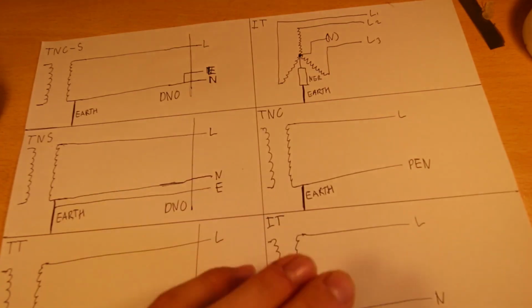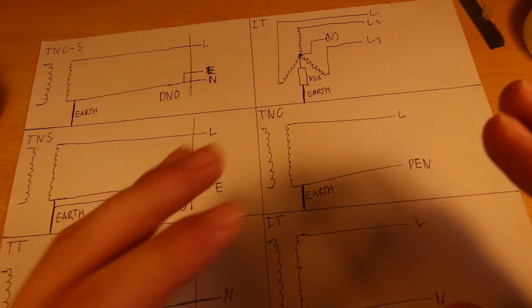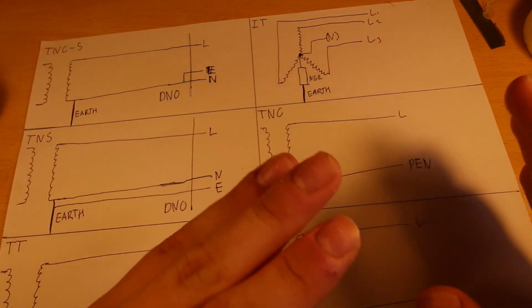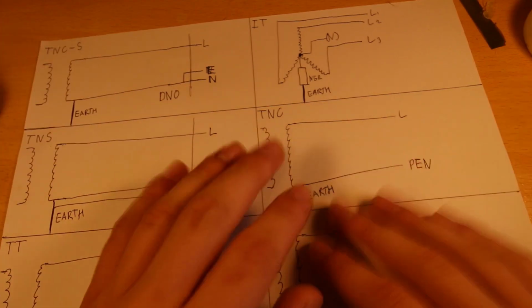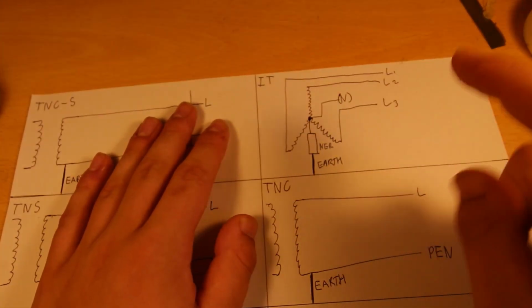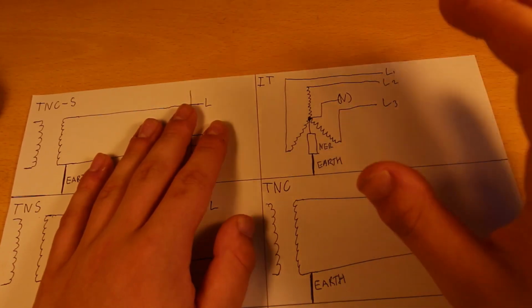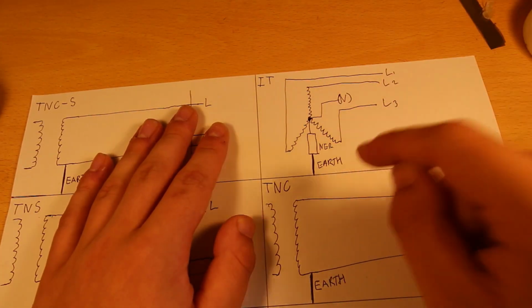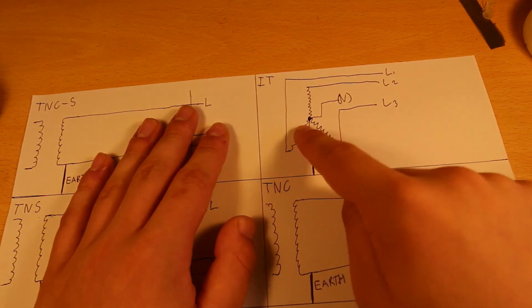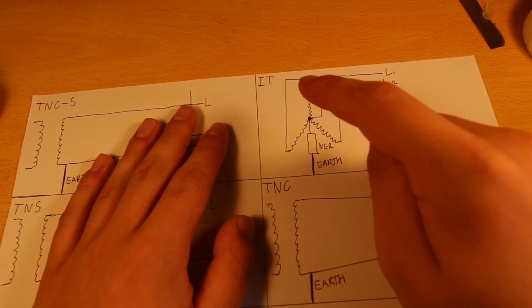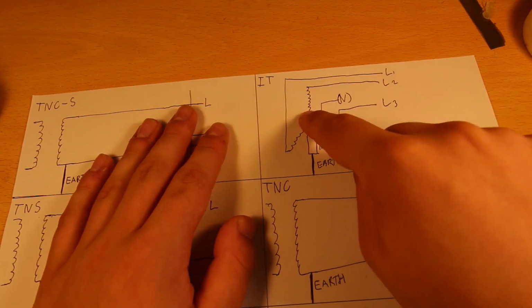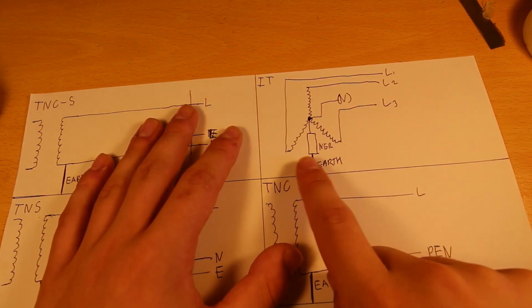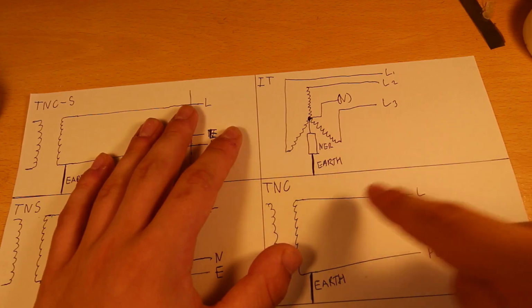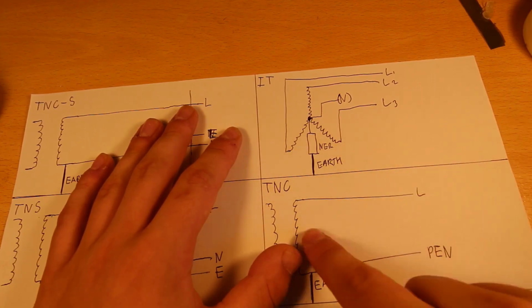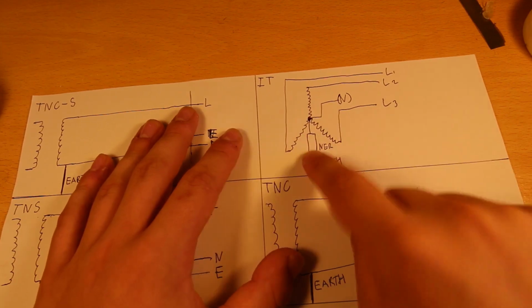service head. We then have IT, which I've drawn twice because there are 2 variations of it. It can either stand for impedance to earth or isolated from earth. This one here is the most common application of it. So on all high voltage distribution in the UK, it is IT earthed. That means you have the 3 phases in a star point on the secondary like this. The point from the middle goes through the NER, neutral earthing resistor, down to earth. That means that your earth fault current is limited by this resistor.